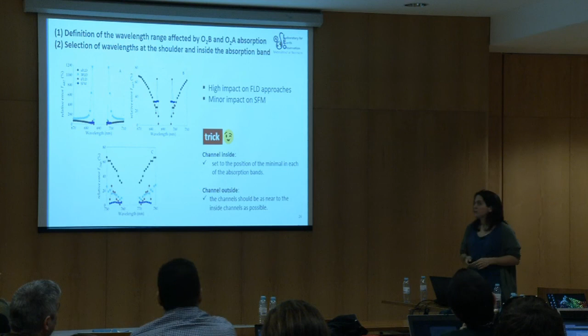And then the last thing, which we didn't do in the paper but is really important, I learned working in Jülich with Andrea. He made a really nice setup to validate the flux. Once you have your instrument characterized and your retrieval method implemented, do some validation. Before you start measuring vegetation, take targets that are not fluorescent, measure, retrieve, and see the fluorescence value. If on a non-fluorescent target, like a gray panel or soil, you get positive values of fluorescence or really negative values, there is something wrong. So before trying to use fluorescence to understand the physiology, do this kind of validation.